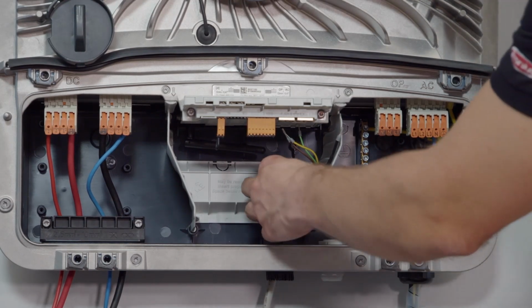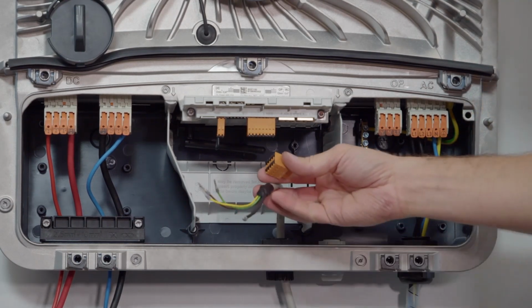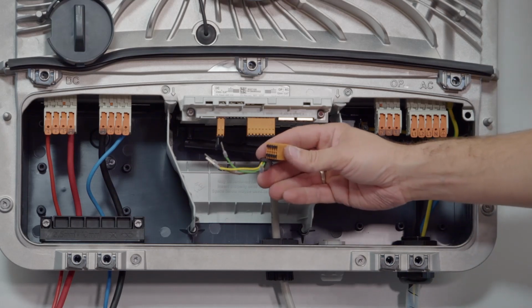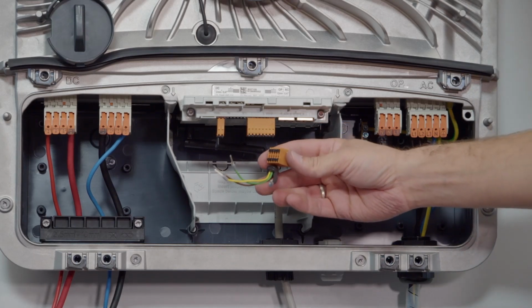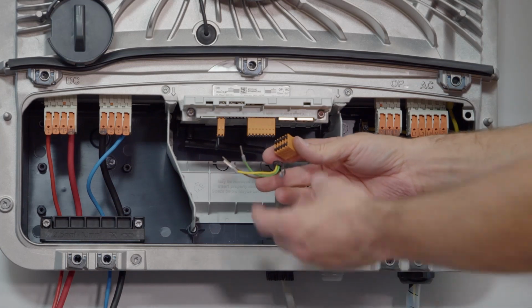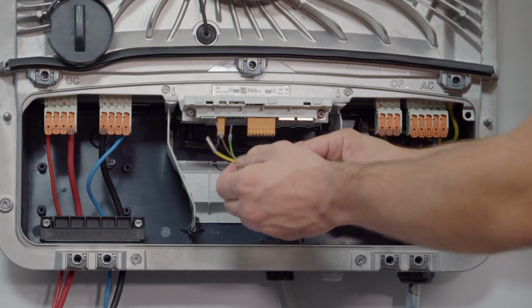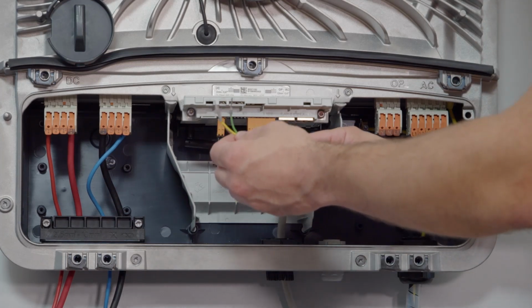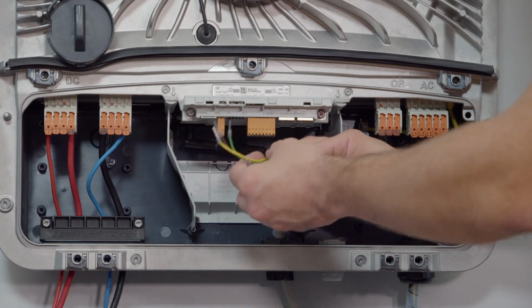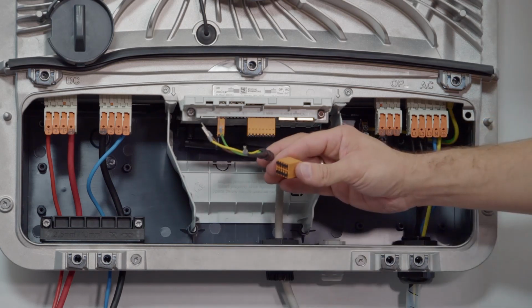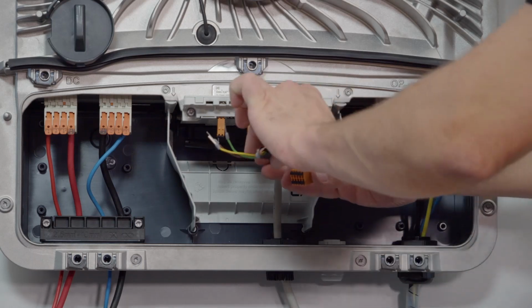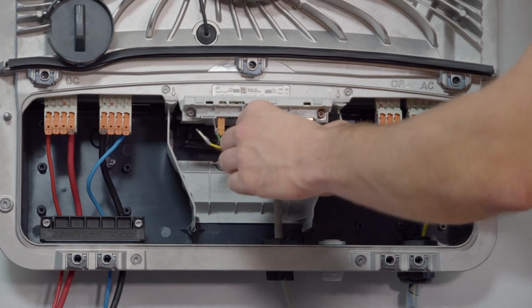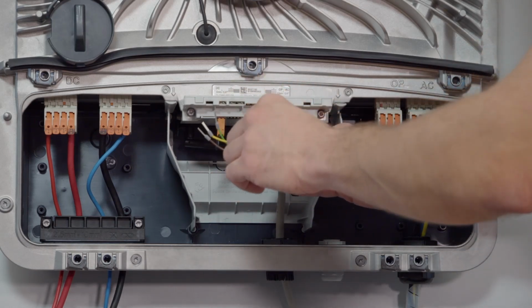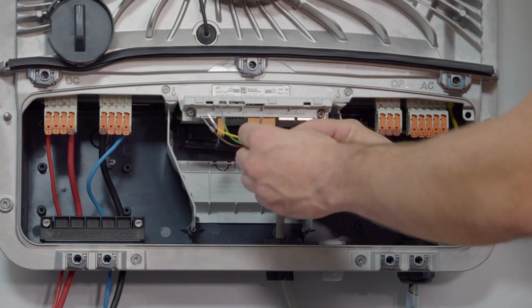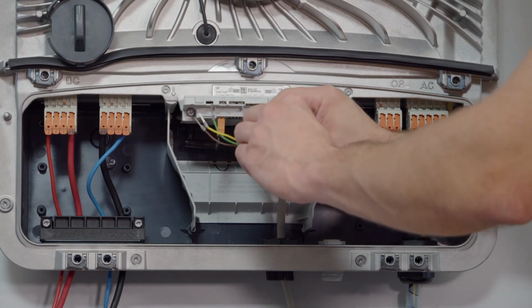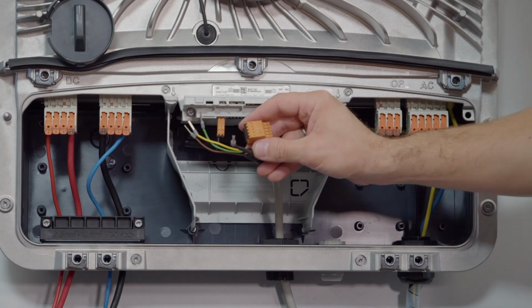Very important for the data communication, we need a Cat5 or Cat6 cable to do the data communication between the Modbus lines. Please note, whenever you use such a cable, make sure that the cable pairs are twisted and that you have a data shielding on this cable line. Whenever you have a shielded cable, please make sure to ground the shielding of the cable, and with us you can do it directly with the shield contact here on the data manager plug.